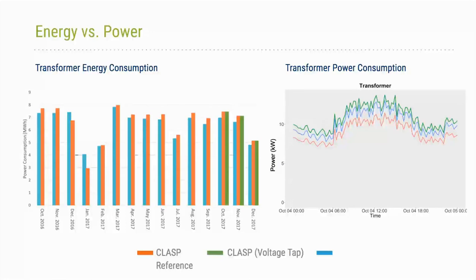And here I have a graph about energy versus power for the transformer. The transformer was interesting in the sense that the load was always above around 6 or 7 kilowatts. So there weren't large swings in the power profile. So the vendor technology did perform better. I think we recorded an energy error of around 7%. However, here we're showing two things: the CLASP standard technology and the one with voltage tap, which we would expect to increase the accuracy of the sensors because now we would actually have voltage measurements. But through the experiment, we deployed this voltage tap technology for 3 months, but we didn't see much of a difference. I think it was around 1% improvement.